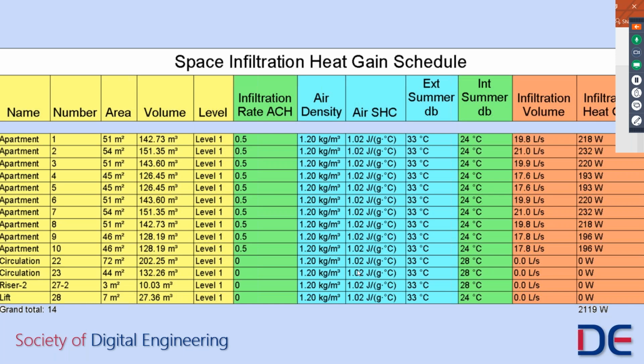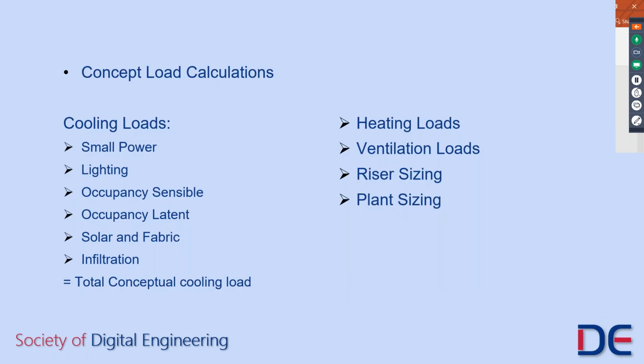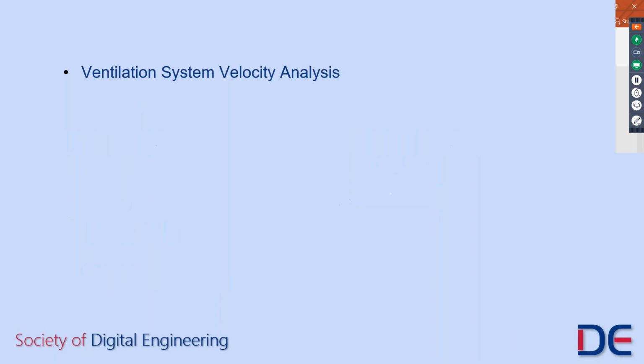And this is perfectly adequate for an early concept design level cooling load. To do the full cooling load, we can actually create schedules for small power, lighting, occupancy sensible and latent gains, solar and fabric infiltration. We could combine together all of that into one single schedule, which will create the entire conceptual cooling load. We can do similar things for heating loads, ventilation loads, riser sizing, plant sizing, and anything else that can be calculated through the parameters that we've made available to ourselves and will be automatically updated as the building changes over time.